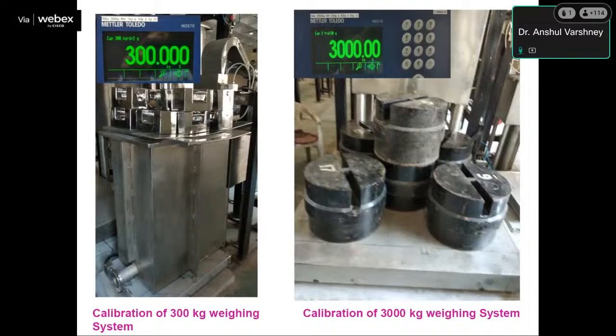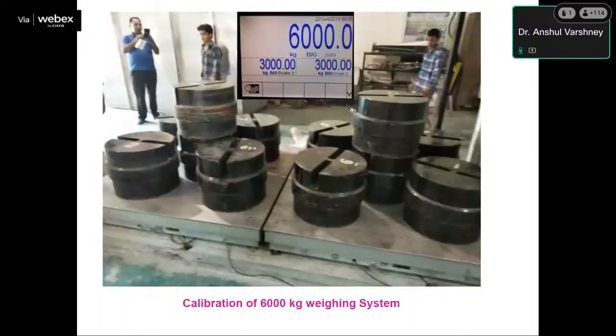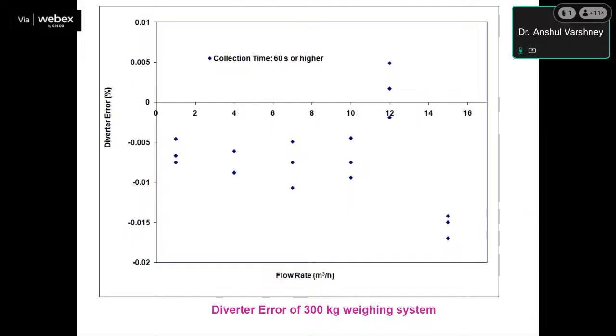And for our weighing system verification, we have different types of weights. For a specific period of time, we are verifying the performance of our weighing scale with the help of standard weights. Like you can see, for 300 kg it is exactly showing 300 kg, for 3000 it is exactly showing 3000 kg, and this is for 6000 kg. We have standard weights for the verification of our weighing scales.